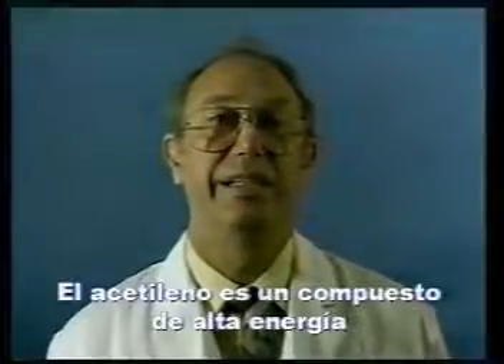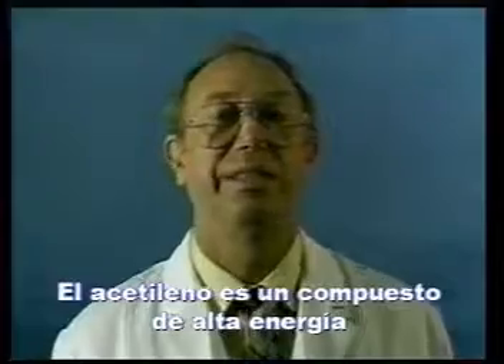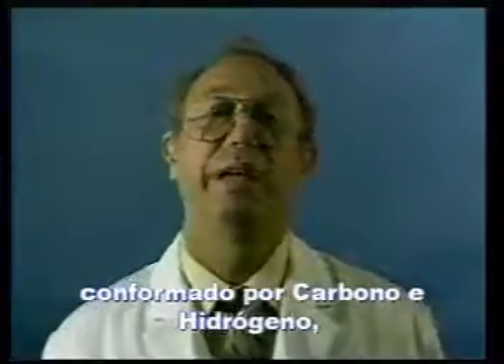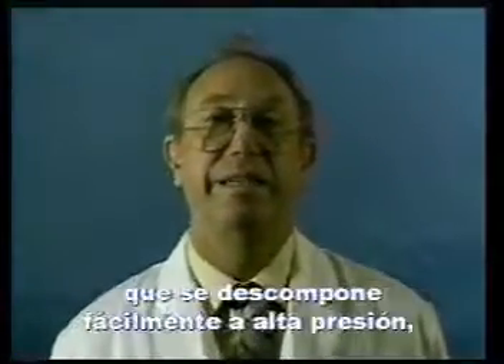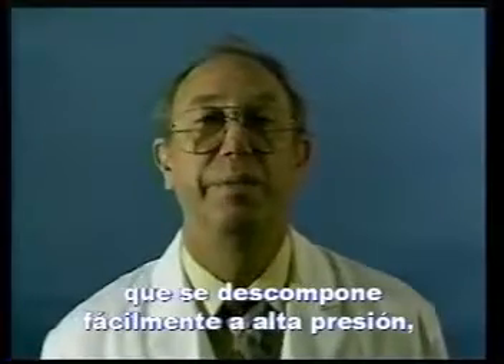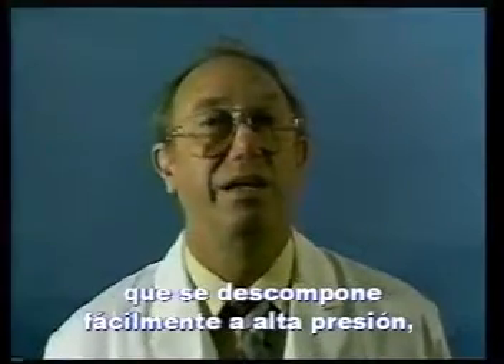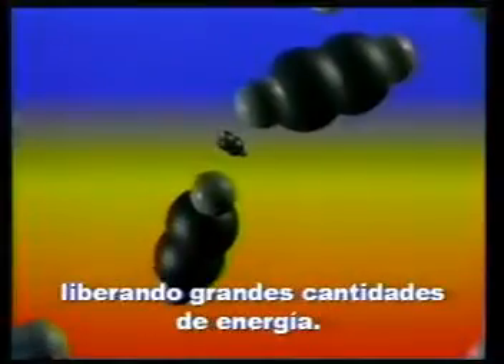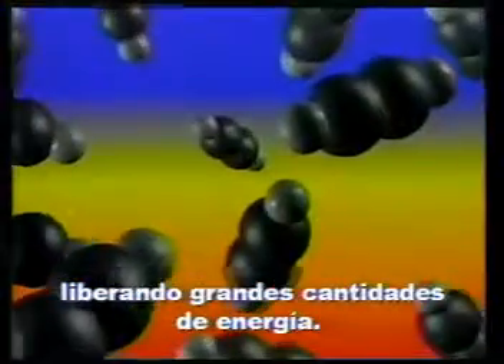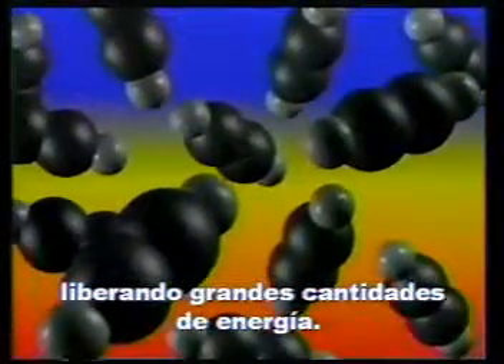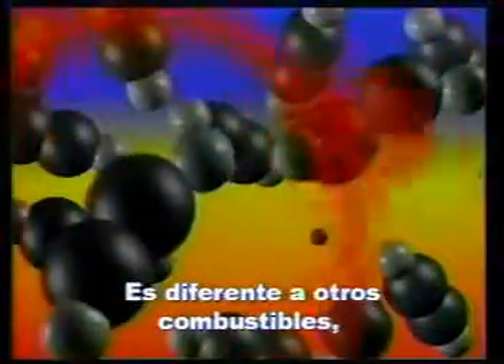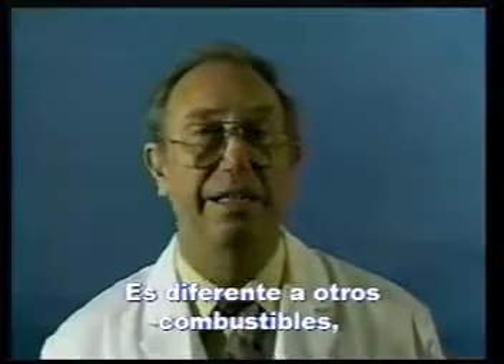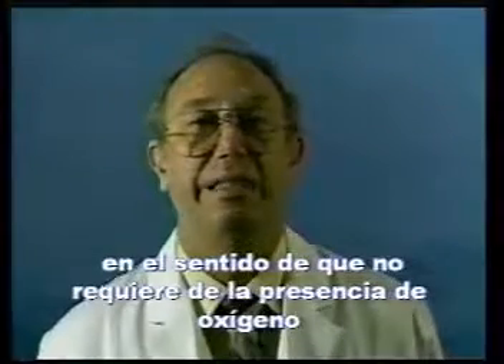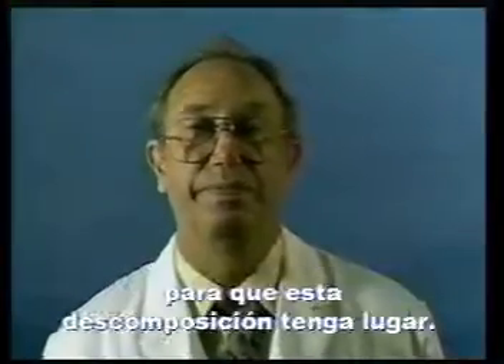Now let's look at acetylene. Acetylene is a high energy compound consisting of carbon and hydrogen, and acetylene is different compared to other gases because it is a combustible gas which may decompose. That means that it will fall apart into its atoms, carbon and hydrogen, releasing large amounts of energy. And there is no oxygen needed as in other combustions.